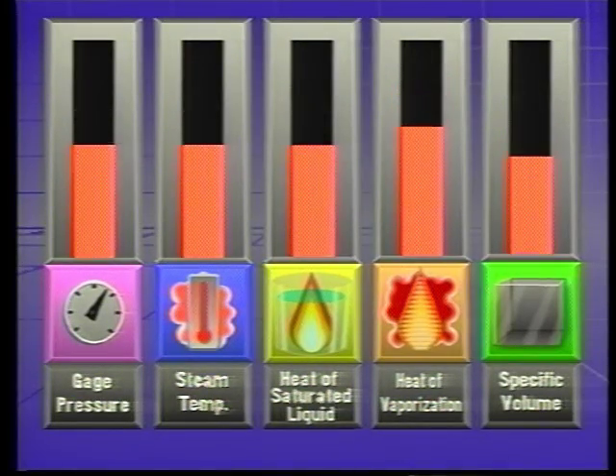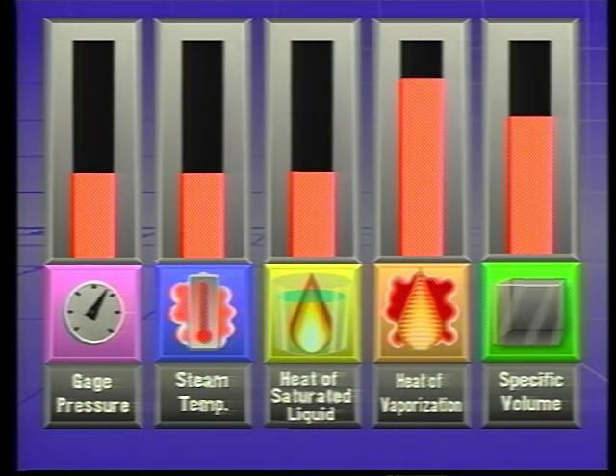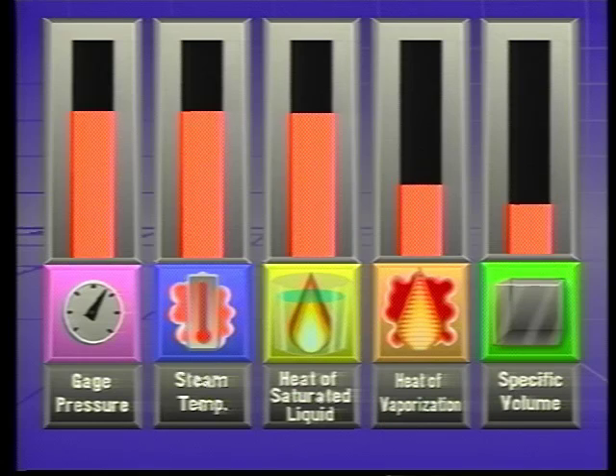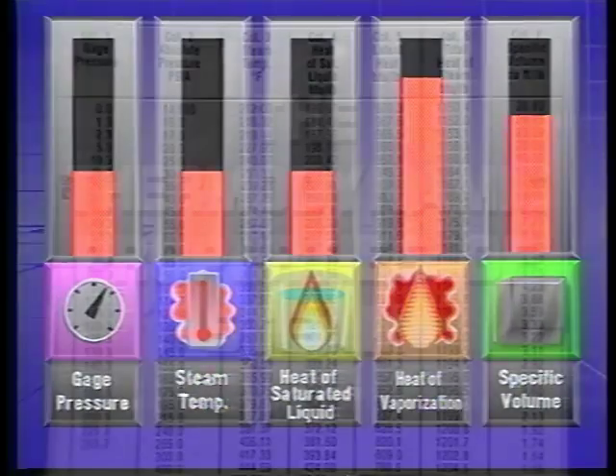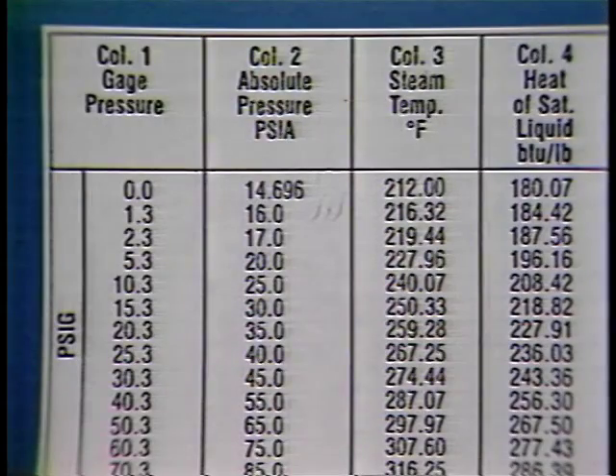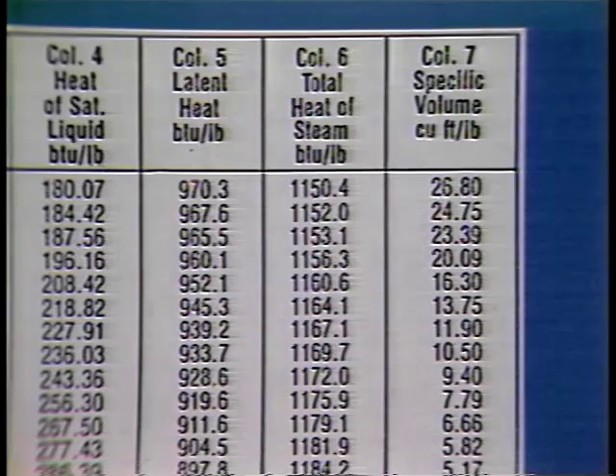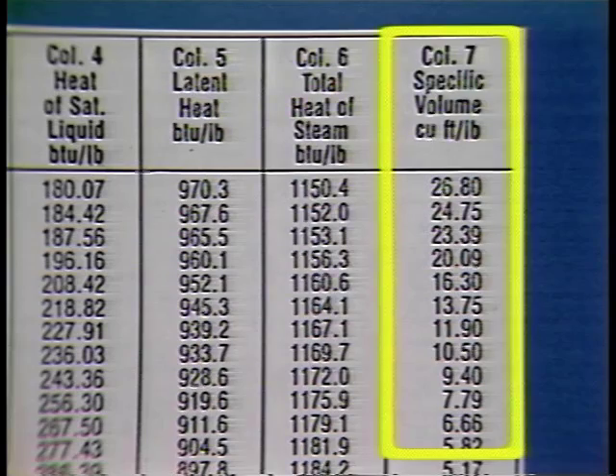The effect of changing pressure on steam temperature, the heat of the saturated liquid, the heat of vaporization, the total heat of the steam, and specific volume are recorded on a table called the thermodynamic properties of steam — a standard industry reference. If a specific temperature is required for a process, the tables show the pressure at which that temperature occurs. The specific volume column can be used for flow rate calculations.